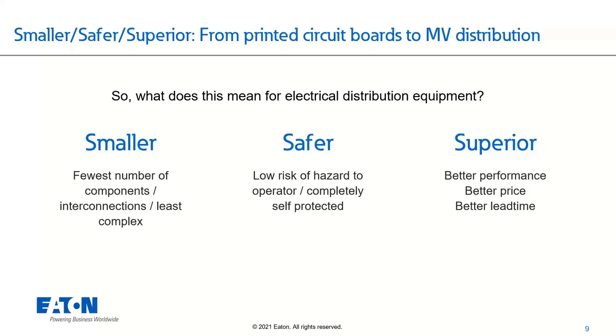And obviously more safety for the operator is better, but there's another piece to that puzzle, and that's equipment safety. You can imagine that you would have maybe a low voltage assembly, and if I had an arc flash incident in there that was relatively safe to the user, their arc flash boundary was enough where the user's in a pretty safe scenario, but my equipment damage is still fairly high when I'm in that level two zone. And that's something I want to make sure of, from a standpoint of how do I get that equipment back online? What's the total capital cost? Downtime and outages is obviously another very big piece. So how can I increase safety, not only for my operator, but also for my equipment, and ideally increase the longevity of that piece of equipment as well, and keep my costs for fixing something like that as low as possible.